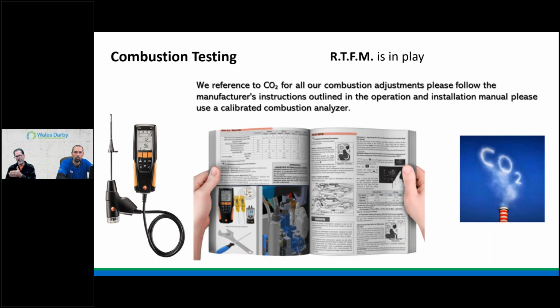So this is the means and the needs, and this is not just for modern day heating boilers, right? This is regardless of fuel, regardless of appliance. And it is the fact that if you're not comfortable with a combustion analyzer, you're not necessarily, one, achieving the efficiency, and two, you could be making a byproduct that could be dangerous as well. So we have CO2, and we have carbon monoxide. So we have the parameters to play nice, and there's that safety and the efficiency that we want to achieve within doing that.